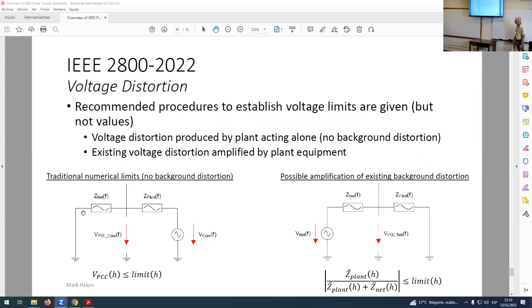But almost, I thought we were done. I think this is the last one. Okay, what about voltage distortion? There are no voltage distortion limits given in 2800. There were no voltage distortion limits given in 1547. In 1547, there wasn't even any discussion of voltage distortion. In 2800, there is, okay? But no numbers are provided. It's left up to each utility company for each interconnection to determine and specify limits on voltage distortion that can be produced by an inverter-based resource interconnection.